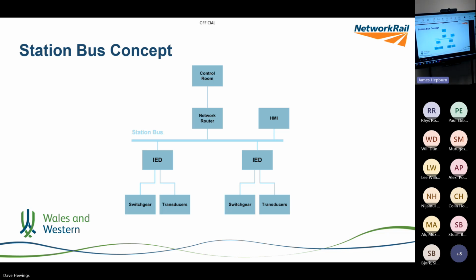And what we've done for the first time in Great Western is take that concept outside the substation. So we have substations that talk to each other during faults, during 10 milliseconds of a fault, and they pass information of the fault. So the protection system is now cooperative.